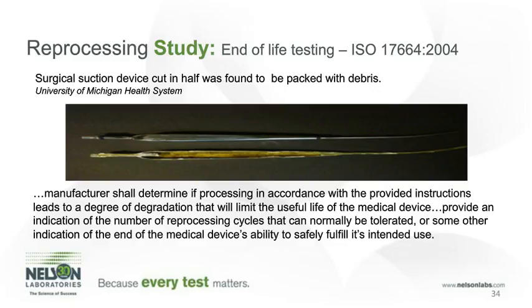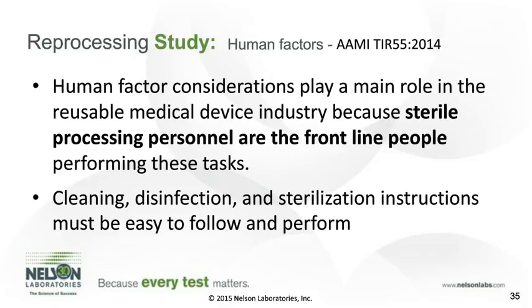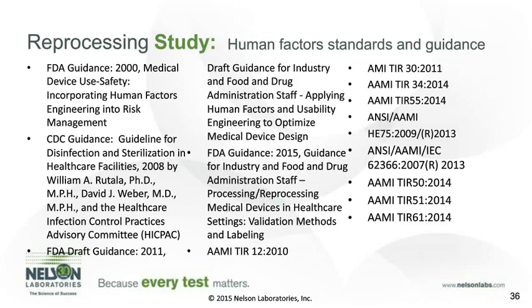Human factors considerations play a main role in reusable device testing, as the sterile processing personnel are the ones that perform this cleaning, disinfection, and sterilization. It is very important for them to perform it correctly to ensure that the healthcare-acquired infections are at the very minimum amounts. There are many standards and guidance that are focused on human factors, and I have added them into this slide. There are many AAMI documents, as well as FDA guidance, CDC guidance, and also ISO guidance.